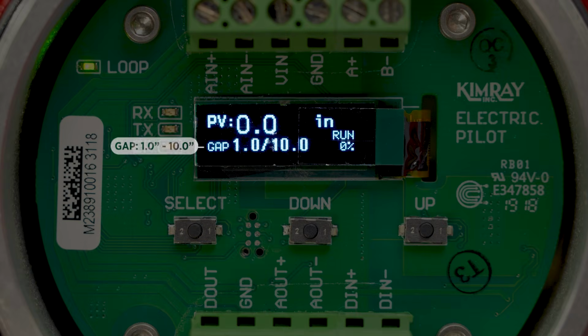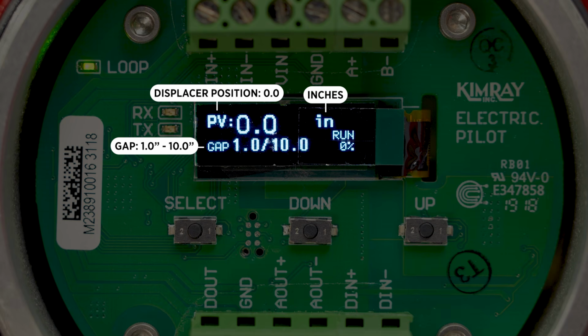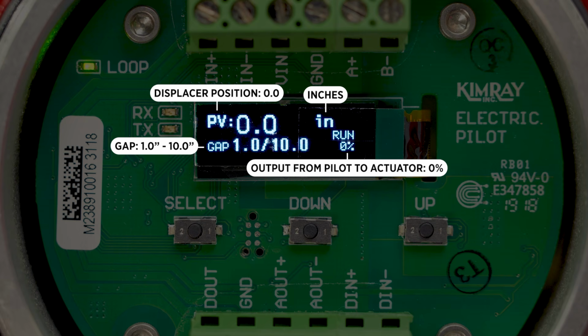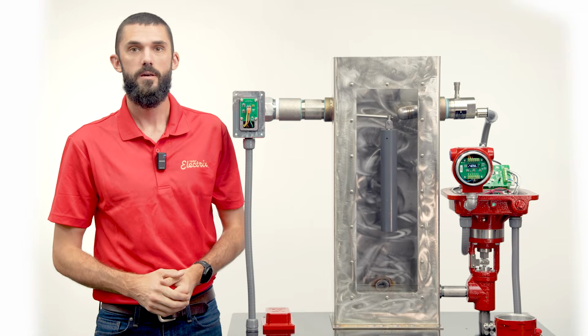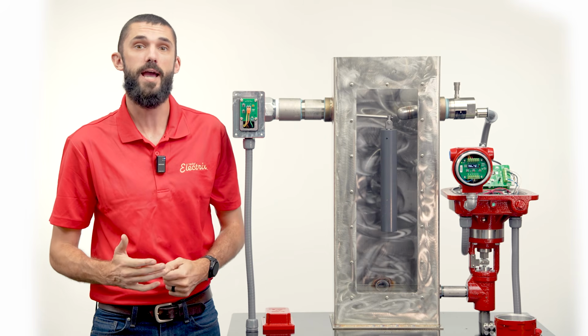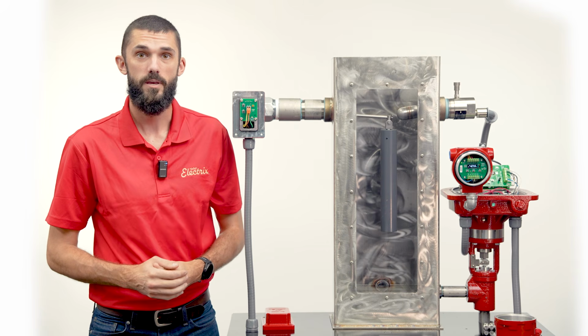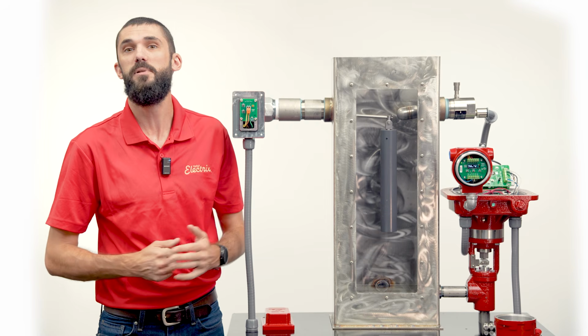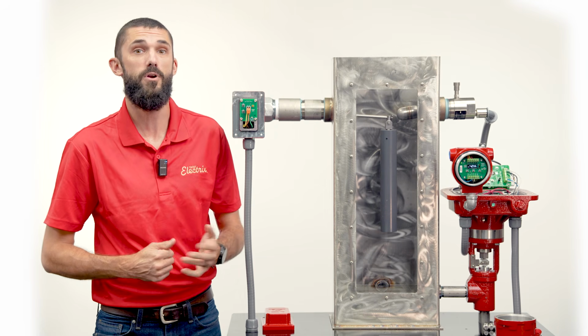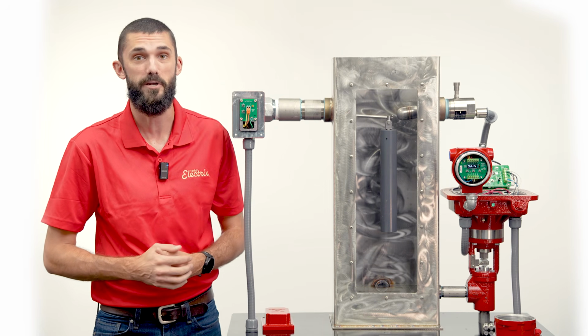Now you can see several things on the home screen. We are controlling from 1 to 10 inches. The PV is the position of the displacer and it's reading 0 because we have no liquid on it. We are reading in inches. Our output from the pilot to the actuator is 0, and the pilot is in run mode. The electric level sensor comes factory calibrated for top level control. If this is your application, this completes the process. You can now turn on your flow and confirm everything is working correctly.